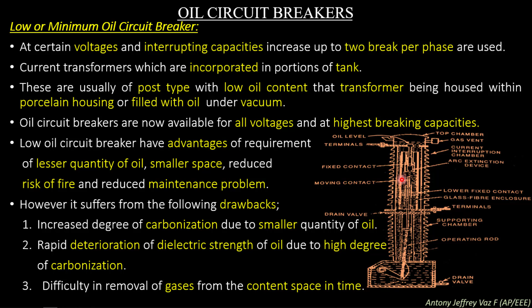The third one is difficulty in the removal of gases from the contact space in time. So we know that some gases like ethylene, methane, etc. will be produced in the arcing chamber. So these gases should be removed from the space within time to increase the dielectric strength of the oil as well as to cool down the arc. So within time we need to remove the gases from the minimum oil circuit breaker. So this is another drawback of the minimum oil circuit breaker.